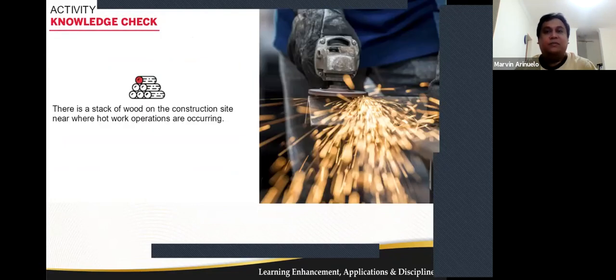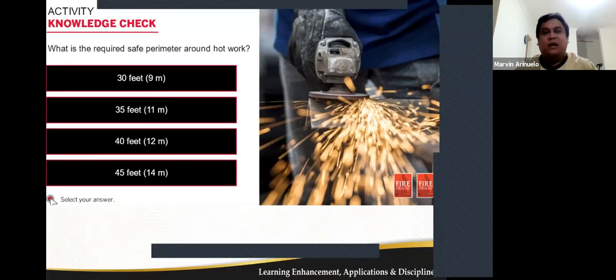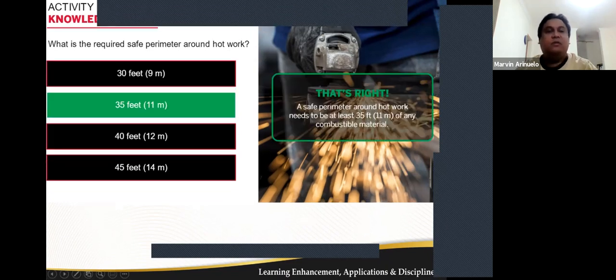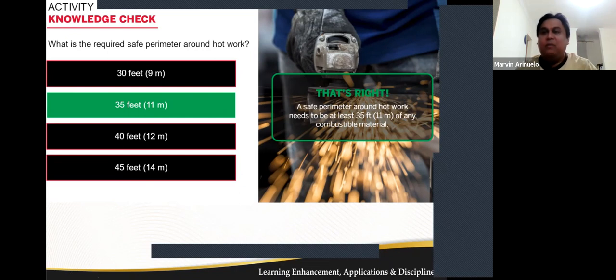Another knowledge check. There is a stack of wood in the construction site near where hot work operations are occurring. Now the question is, what is the required safe perimeter around hot work? We discussed it earlier. If you go to the fire protection handbook, on page 11-51, it mentions that a safe perimeter around hot work needs to be at least 35 feet, or 11 meters, from any combustible material.